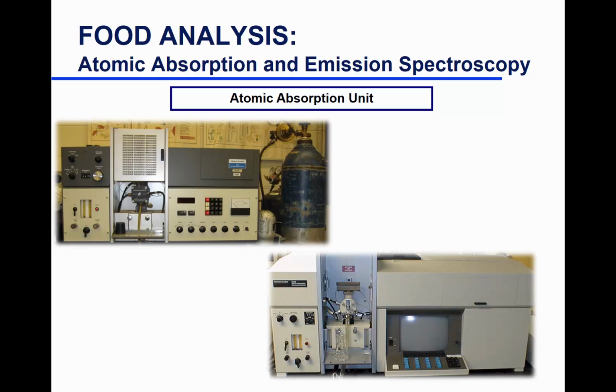The one we have in the lab now is the most recent, and you can put multiple lamps at the same time rather than having to change the lamp each time. And also it has the graphite and the flame, so you can do both types of atomic absorption.